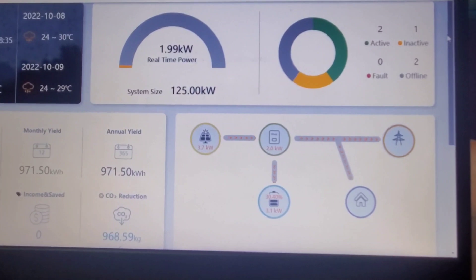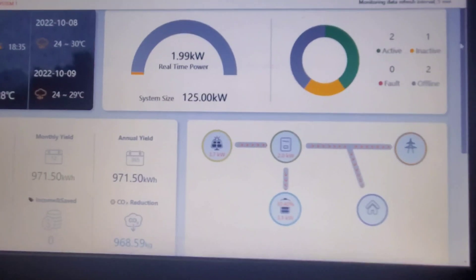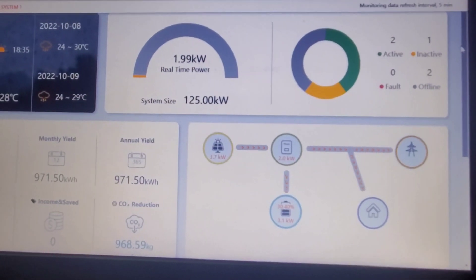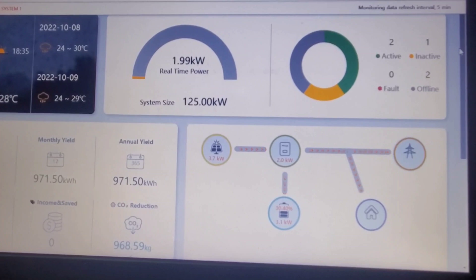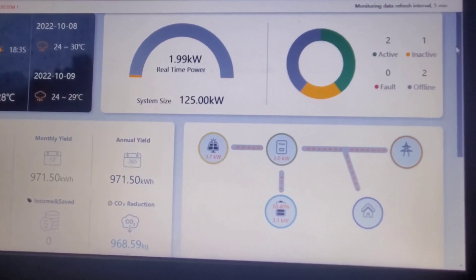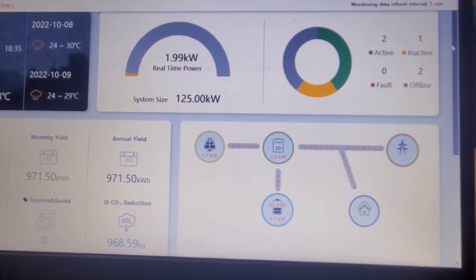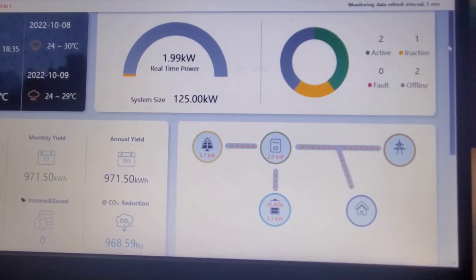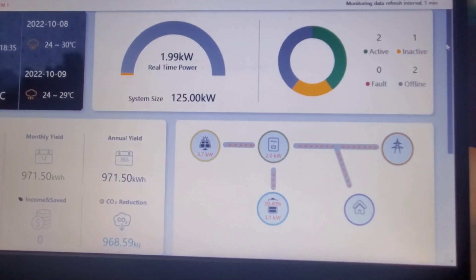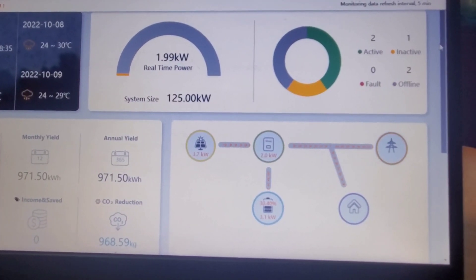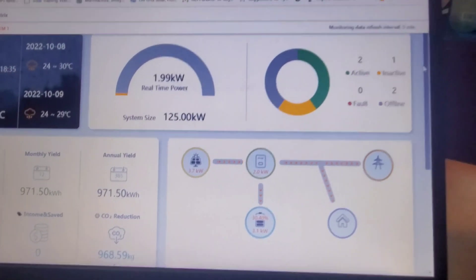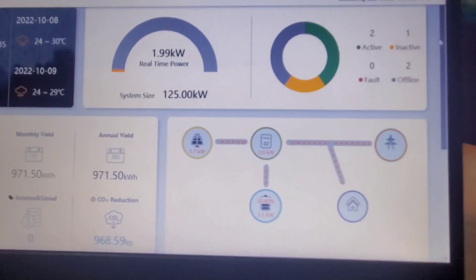The generator connection—we have the cables but haven't connected them yet. The reason is the breaker is not big enough to accept our cable. We have 150mm cables we're using for the incoming from the generator, from the panel room into our room, and then we'll distribute it to the inverters and to the EPS for our box.